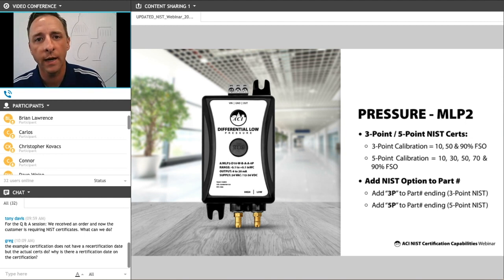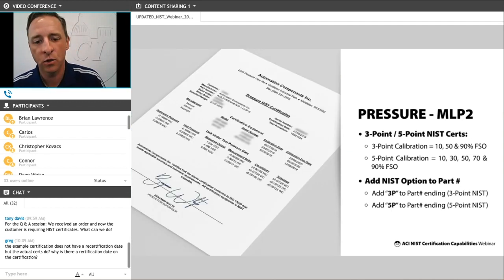Our MLP2 series differential pressure transducers are also available with NIST certs. The ordering process is the same as the DLP — you add a dash 3P or a dash 5P to the end of the part number. Here's what a pressure transducer cert will look like. This specific one was a plus or minus 0.25 inch and a 0 to 10 volt output. You can see the cert shows the voltage readings compared to the inches readings and that it falls within the stated accuracy specifications.